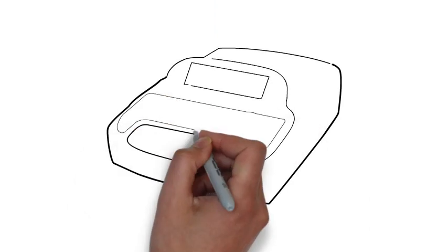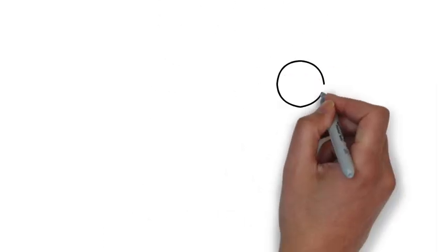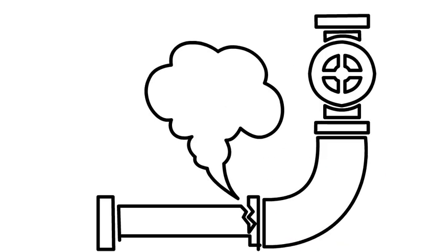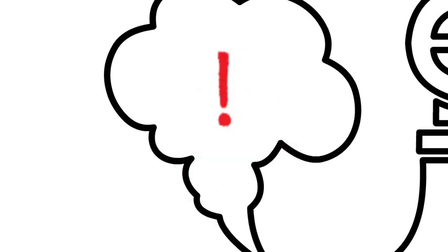Whoa! If the pressure transducer is that sensitive and the test subject is breathing, doesn't that change the volume and pressure in the breathing zone? Well, yes. So the test subject has to hold his or her breath while the leak rate is measured. Furthermore, the test subject cannot move at all, or the pressure will change slightly, and the system will interpret that change as a leak.